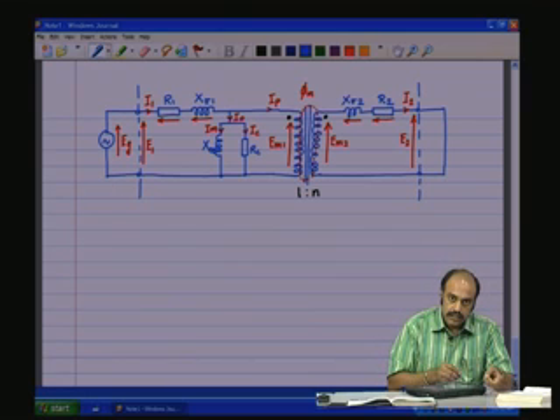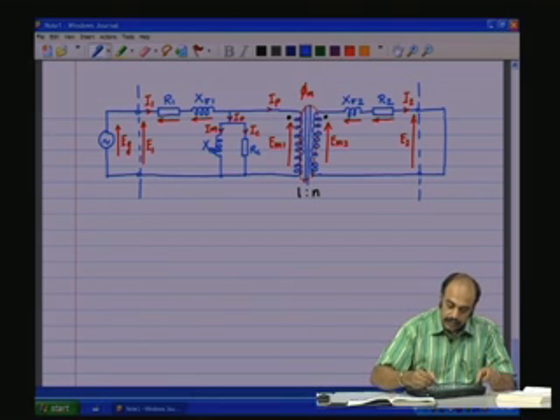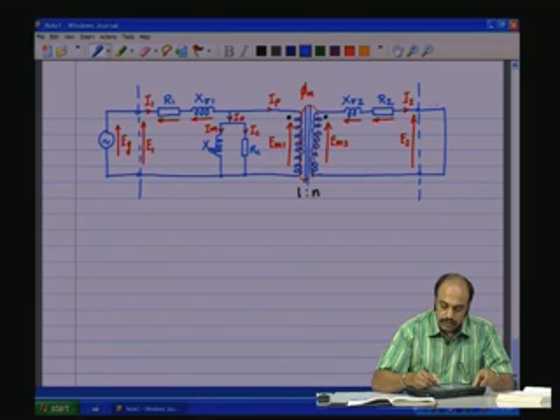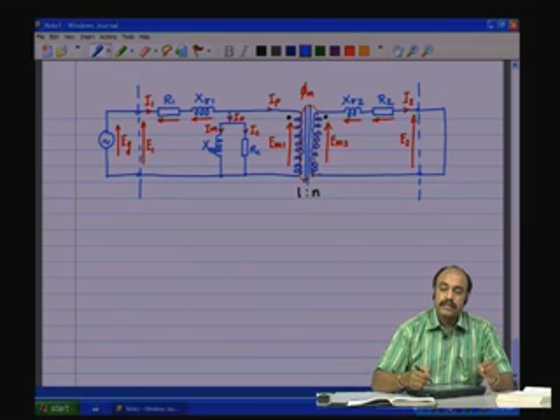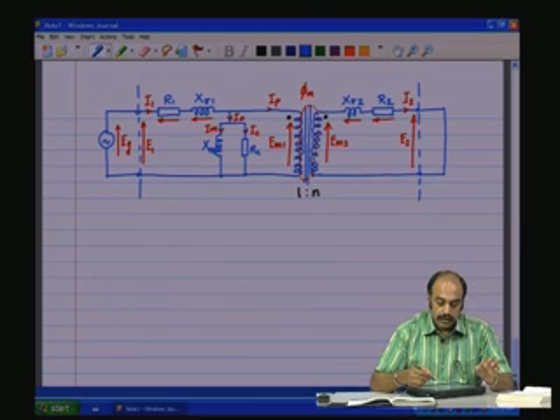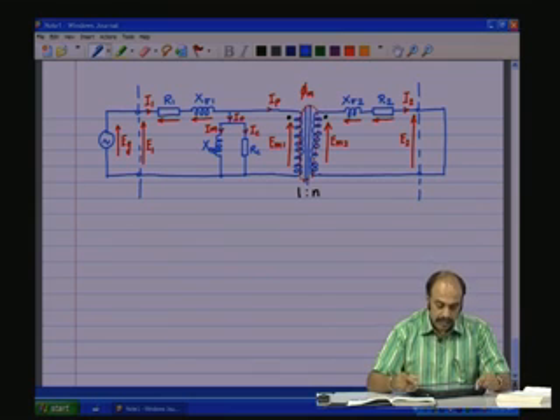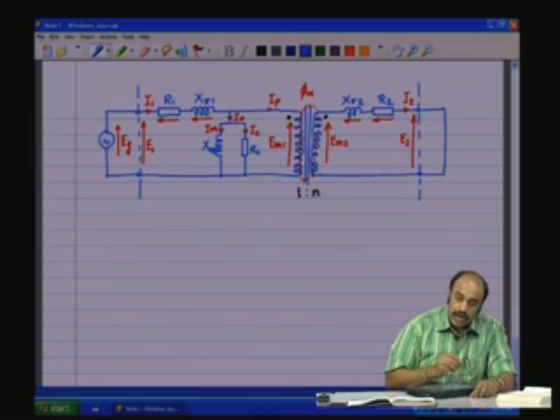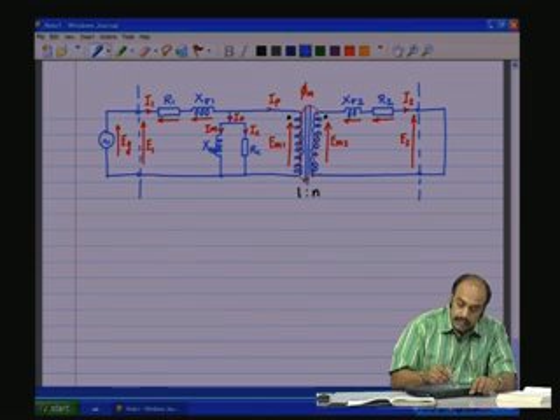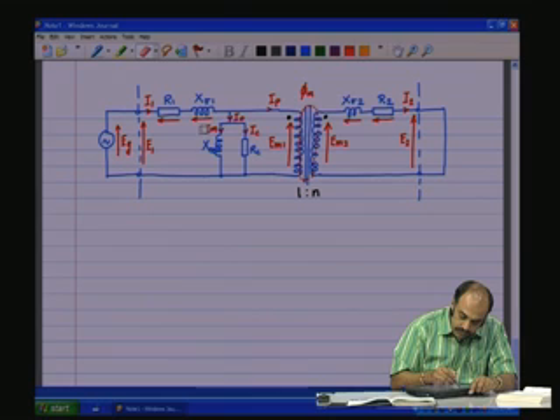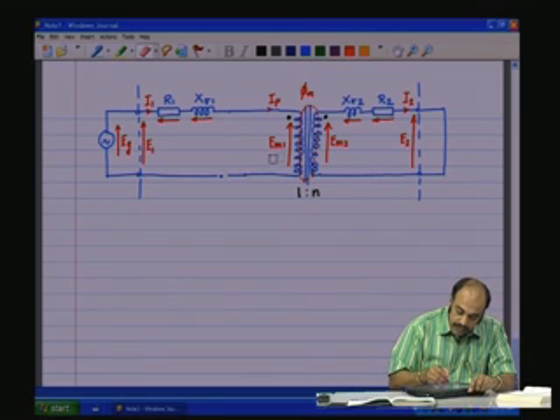You just keep increasing the voltage till the rated current flows through, or the nominal current flows through the secondary, and take the measurements at that time. The measurements can be taken quickly so that the transformer does not heat up. So, under the short circuit condition, we see that the IP will be much higher than the I naught, and therefore, they can be neglected. So, these portions will vanish as they are negligible. And we can do one more thing, as I was saying.